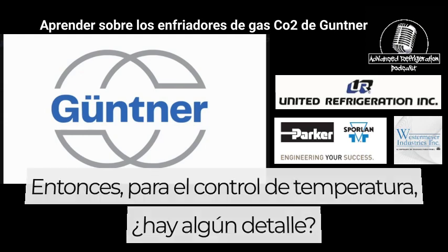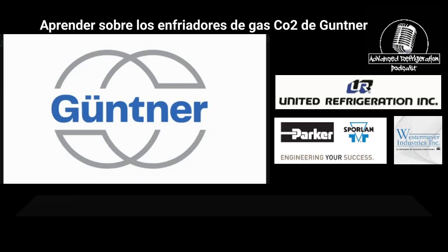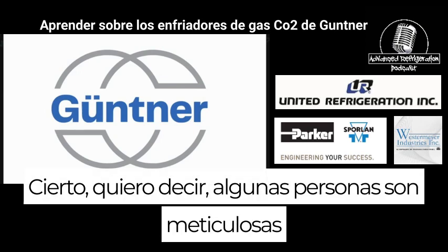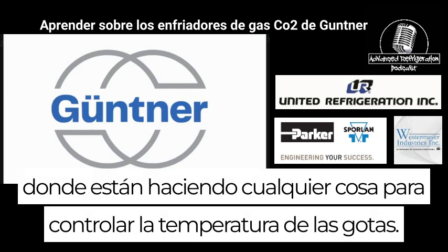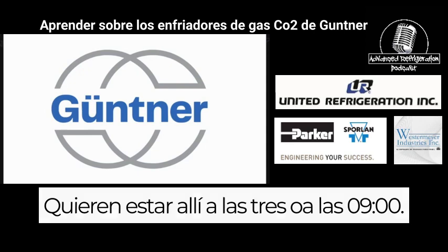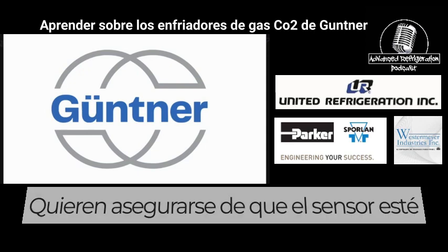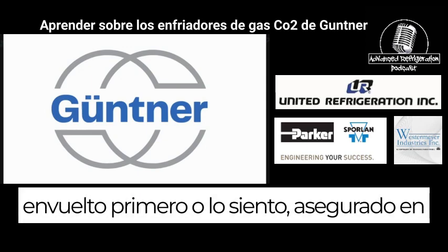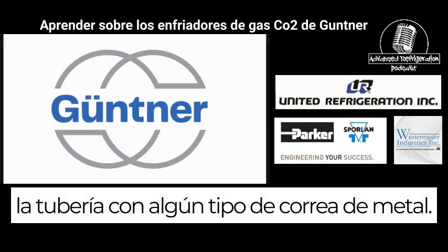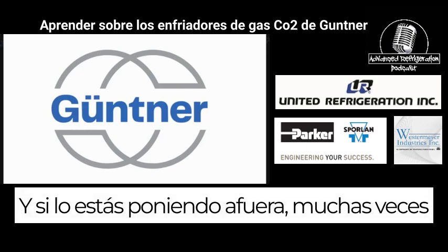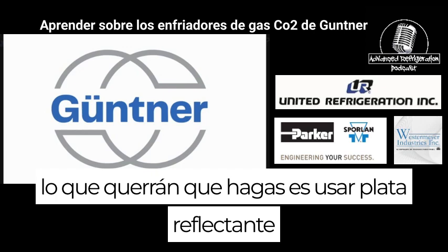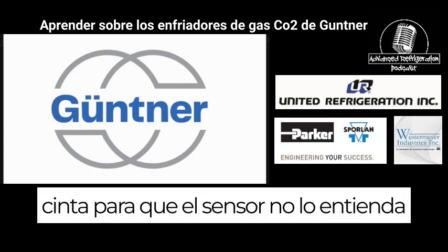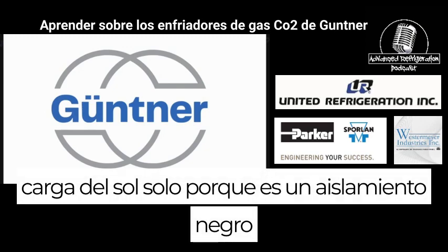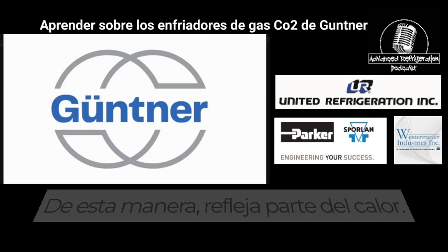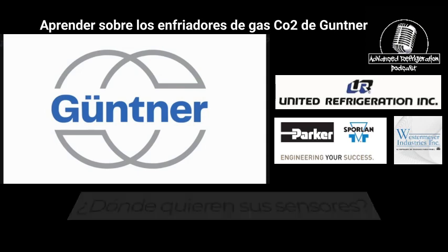Yeah. So for the temperature control, is there any specifics that you want your sensors to be at? Some people are finicky when controlling drop temperature. They want it at 3 or 9 o'clock. They want to make sure the sensor is secured down on the pipe with some sort of metal strap. If you're putting it outside, a lot of times they'll want you to use a reflective silver tape, so the sensor doesn't get that load from the sun, since the insulation tape they use on the outside is black. This way it reflects some of the heat. Is there any kind of specs on where you guys want your sensors?